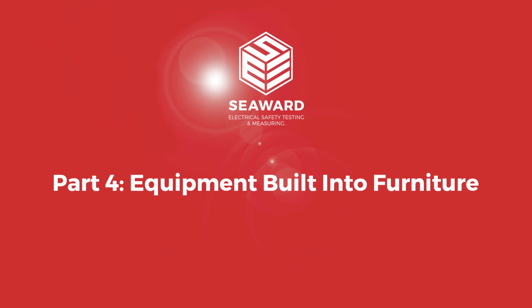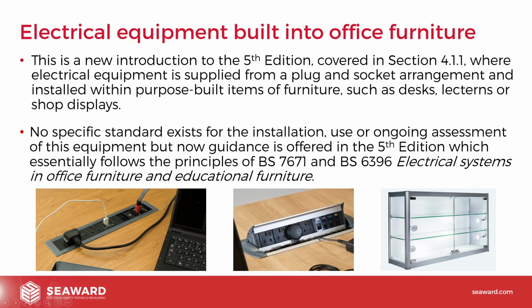Part 4, equipment built into furniture. This is a new introduction to the 5th edition, covered in section 4.1.1, where electrical equipment is supplied from a plug and socket arrangement and installed within purpose-built items of furniture, such as desks, lecterns, or shop displays. No specific standard exists for the installation, use, or ongoing assessment of this equipment, but now guidance is offered in the 5th edition, which essentially follows the principles of BS 7671, that's the 18th edition wiring regulations, and BS 6396, electrical systems in office furniture and educational furniture.